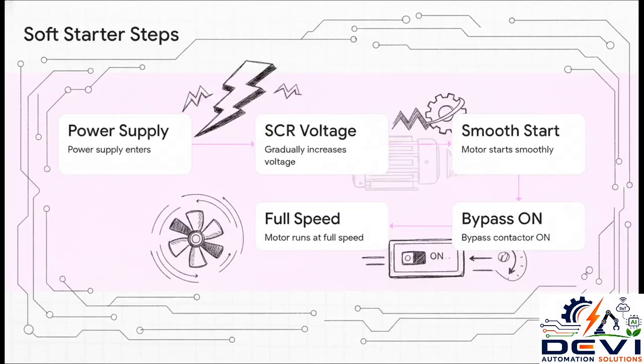So, how does this build into an actual step-by-step working process for the soft starter? Well, step 1, the power supply comes in. Step 2, those SCRs we just mentioned gradually open up, slowly dripping in more voltage. This gives us step 3. The motor starts smoothly without violently jerking the mechanical parts. Once the motor finally hits full speed, we hit step 4. The bypass contactor clicks on. This literally bypasses the SCRs entirely, sending direct line power straight to the motor for step 5, where it just runs continuously at full speed. It is incredibly efficient for what it does.